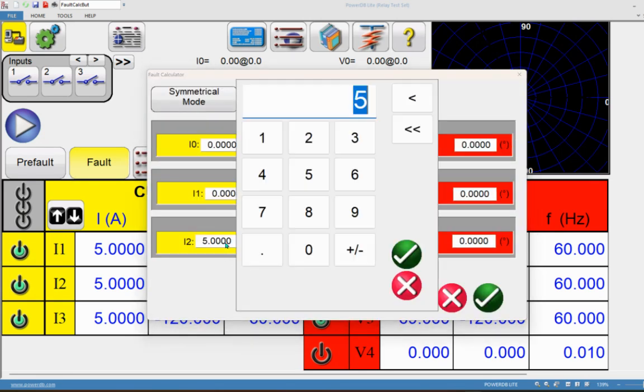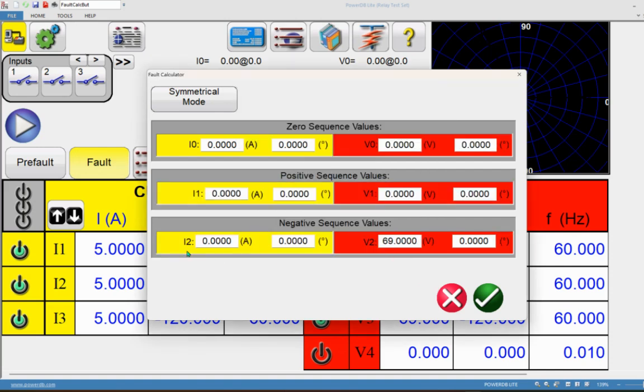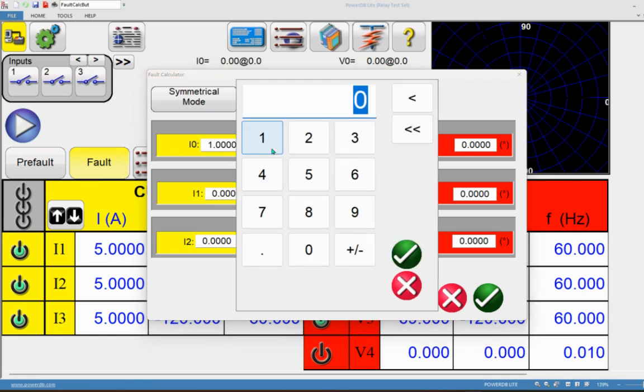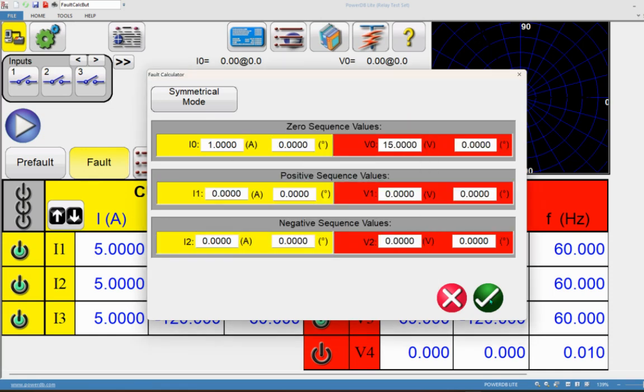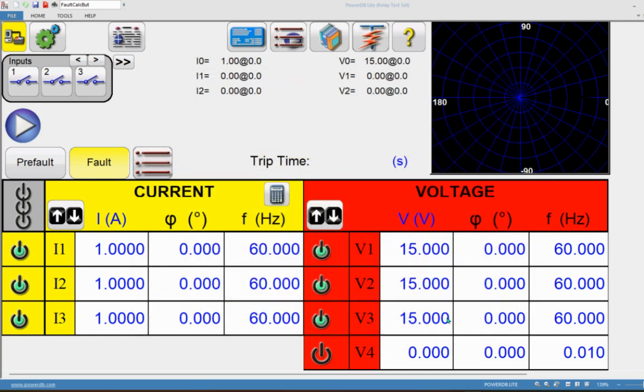Now let's see how zero sequence looks. Set negative sequence current to zero and negative sequence voltage to zero. Set zero sequence current to 1 amp and zero sequence voltage to 15 volts, then click OK. You can see the zero sequence voltage is defined with all phase angles set to zero. Recall from the beginning of the video: zero sequence voltage is the sum of VA + VB + VC, so when all phase angles are zero they all add together as zero sequence voltage.